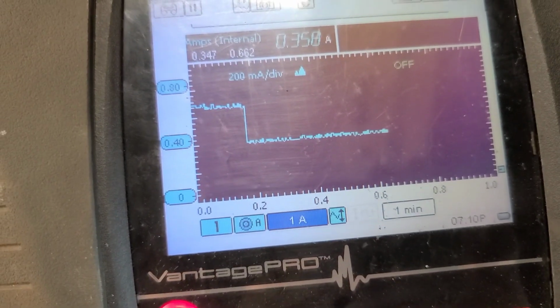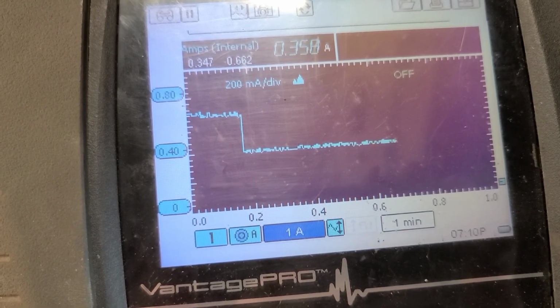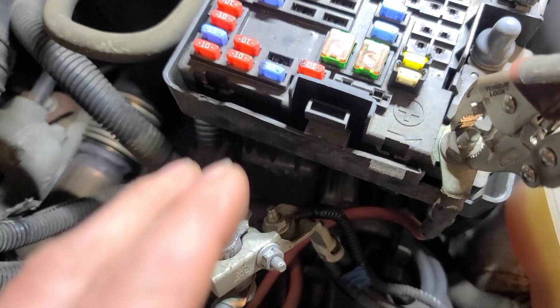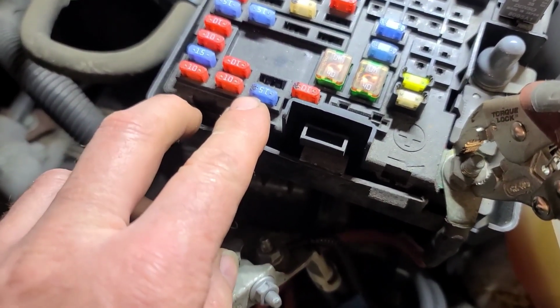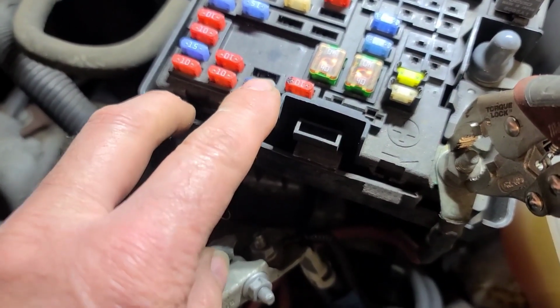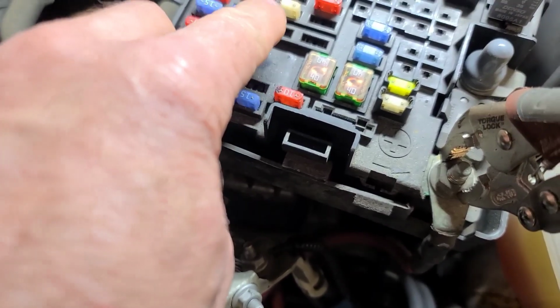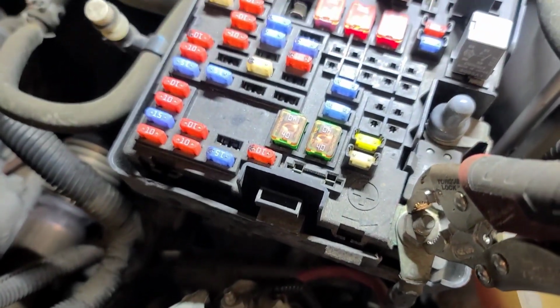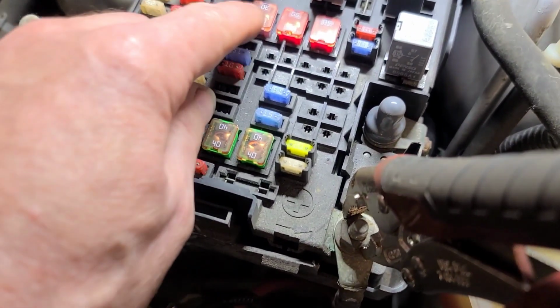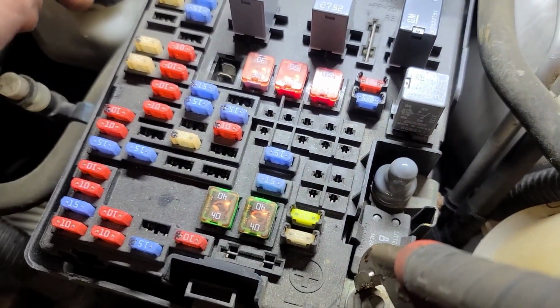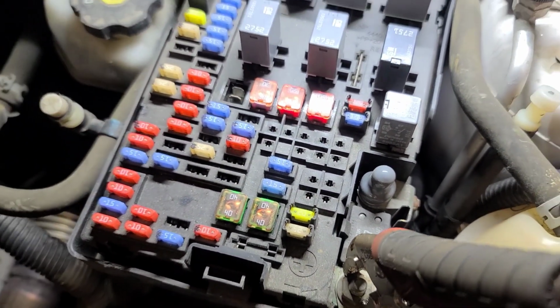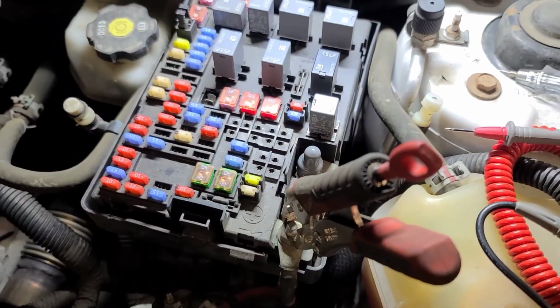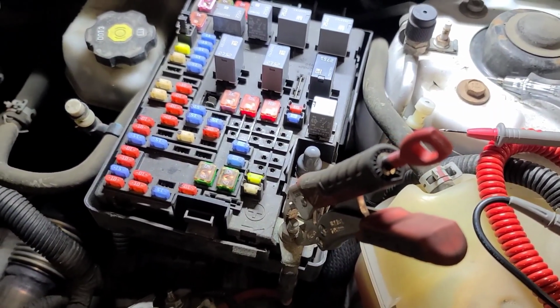So after 38 minutes, it did drop to 198 milliamps. I tested each one of these fuses for voltage drop, testing each one to see which had power, and I put a black marker line on the ones that are live. I tested every fuse for a voltage drop, including popping the caps off. I dropped one of the caps on these maxi fuses, or these J fuses, and none measured a voltage drop.